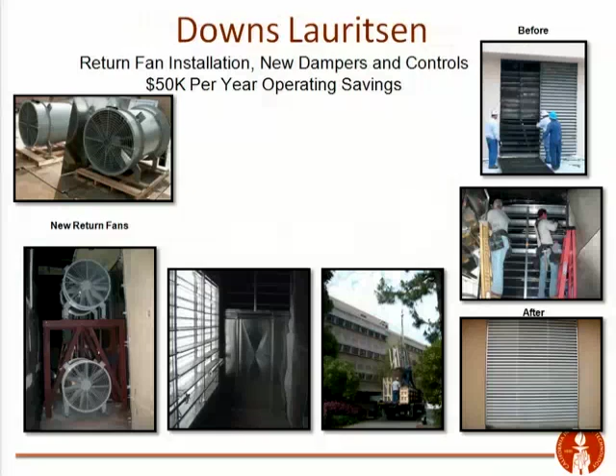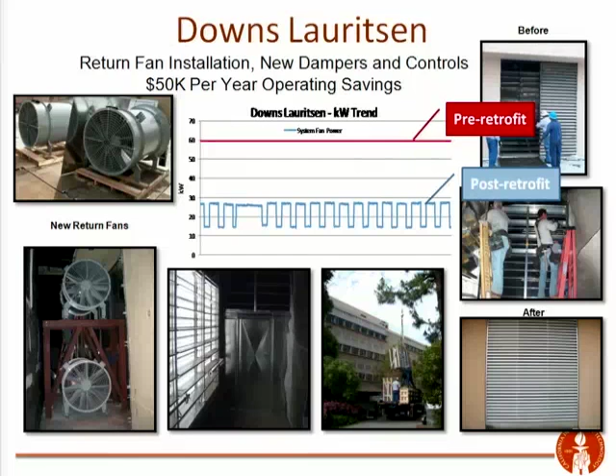This is another project in Downs Lauritsen with a building fan swap out. In the past, we had one fan in this building that was operating 24/7, 100%, just pulling air through that building to cool it, regardless of who was in there, what was going on, or what time of day. We've swapped that out with 3 fans. This is the pre-retrofit energy consumption of 1 fan. This blue here is the post-retrofit with 3 fans. What's important is obviously that's lower, so we've saved energy there. But it also fluctuates because it's a variable speed drive, so it modulates the fan speed based on the demand in the building. So we're not just cranking away 100% all the time, regardless of who's in there doing what at what time of day.